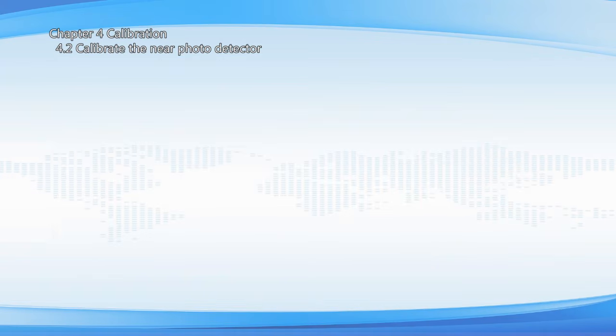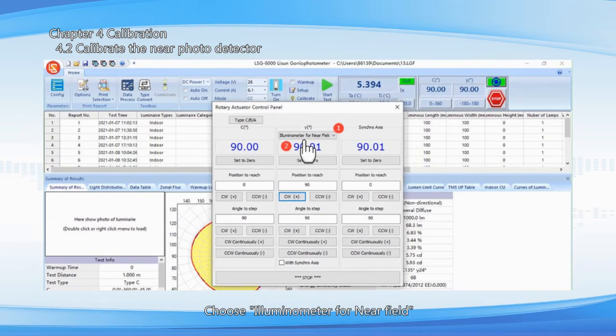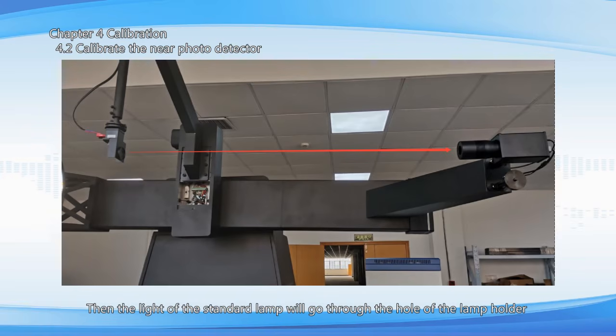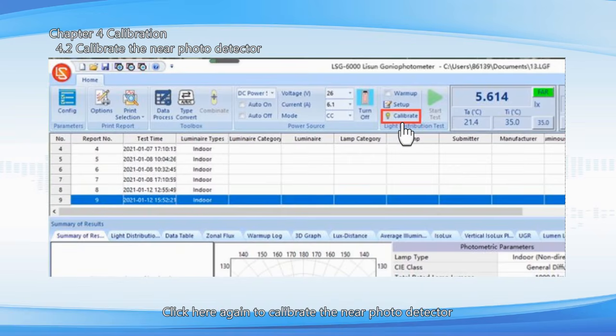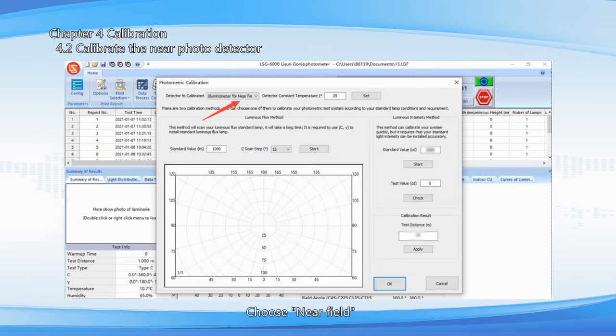Calibrate the near photo detector. Choose illuminometer for near field. Rotate the gamma angle to 90-degree position. Then the light of the standard lamp will go through the hole of the lamp holder and go to the near detector directly. Click here again to calibrate the near photo detector. Choose near field.